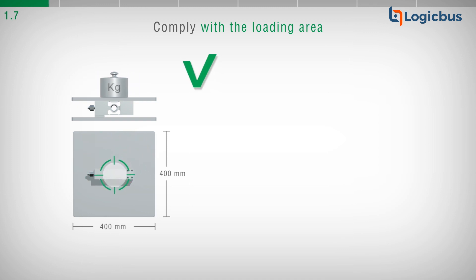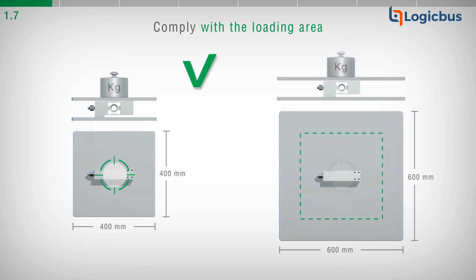By installing a structure with a larger size than that stated on the datasheet, or by applying an object that protrudes from the structure, it is possible to damage the single-point load cell and, in any case, obtain an incorrect weight value.